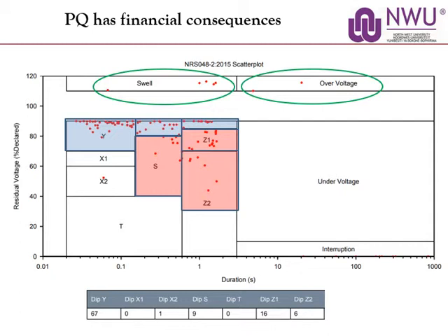Internationally they group in such a way that most sit in the so-called area of compatibility or immunity, compatibility between supply and use conditions. But for sure, if voltage drops to nearly 40% for 1 second, something will go wrong in your plant. We must accept it.